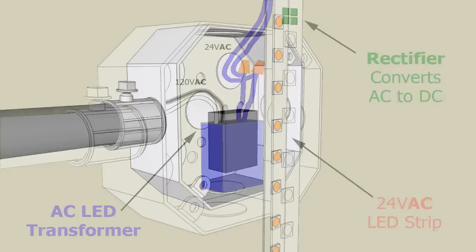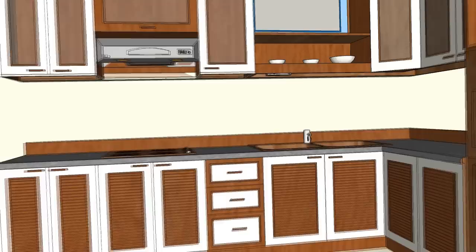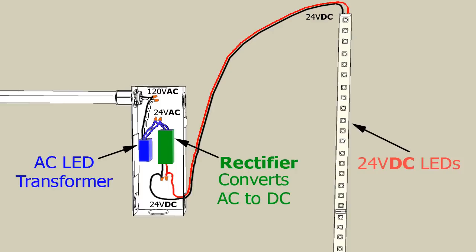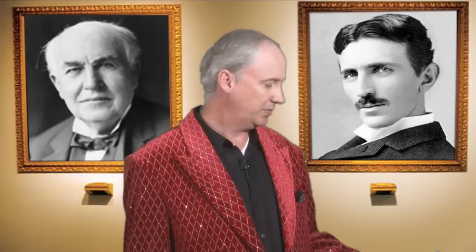A vanity bath bar, for example, would simply use a small AC electronic transformer that's going to fit right inside your junction box. The fixture would convert to DC using a rectifier right on the LED circuit board. For larger systems like soft strip or light channel, we would use a larger remote located DC power supply. In a remote power supply, voltage is reduced and the power is converted to DC with the rectifier right in the same power supply box. If you use a remote located power supply where you're converting your high voltage to low voltage and your AC to DC in one box, you get about 25% more light using the same amount of energy. I like efficient design.